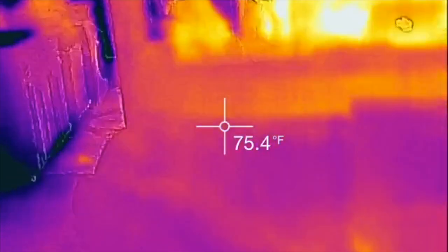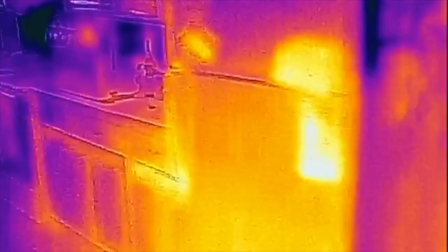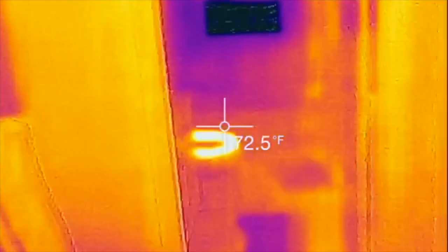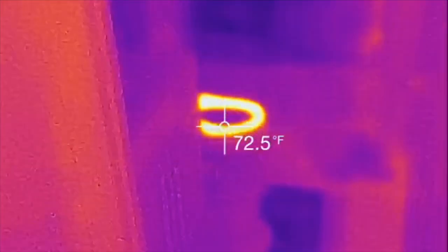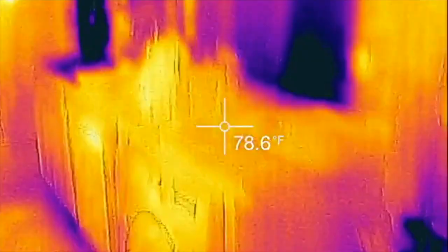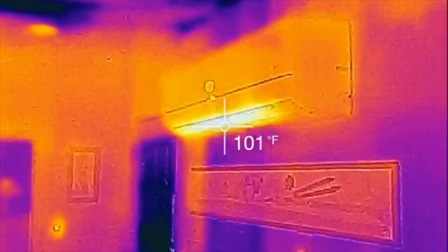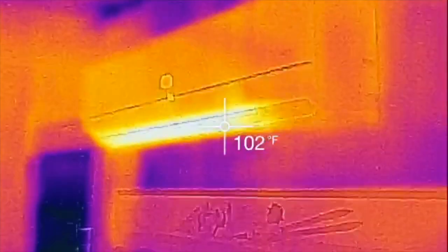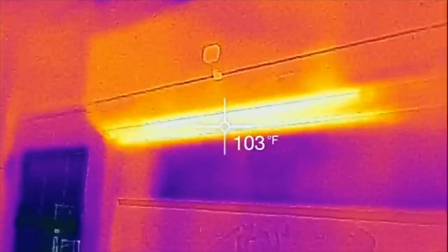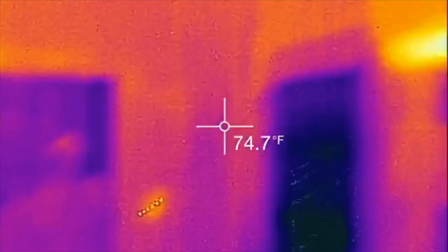That's a couch at 75 degrees. That is a refrigerator. That is a heated toilet seat — that is the only auxiliary heat in the building. You can see there's more electric baseboard back there. Second year running it. If you go outside, the thermal camera can't even read the temperature it currently is, but the air coming out is probably close to negative 30 to negative 40 degrees, because it's making cold outside and making heat inside. That's the concept of the heat pump.